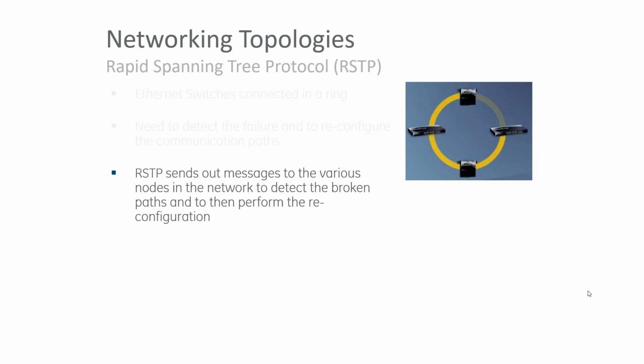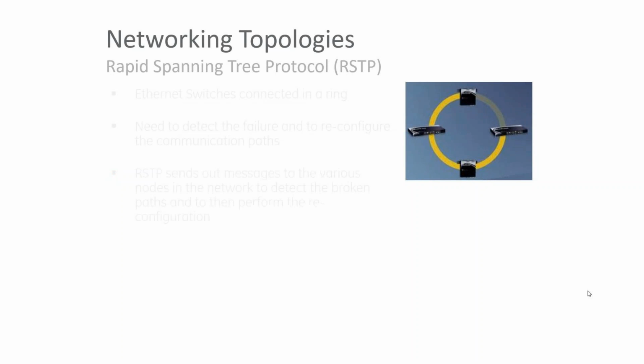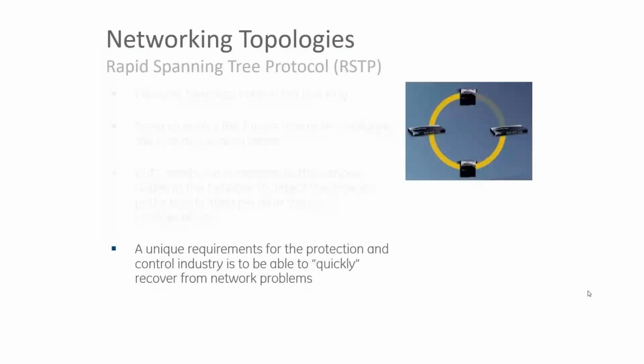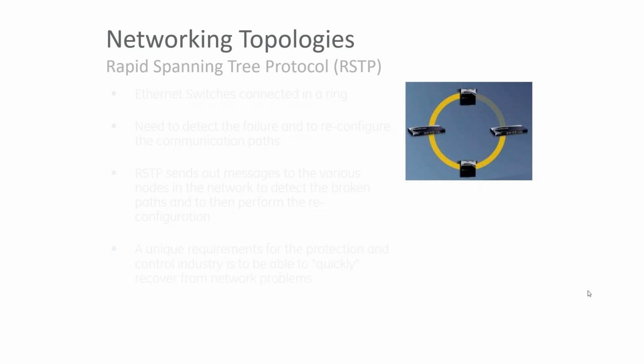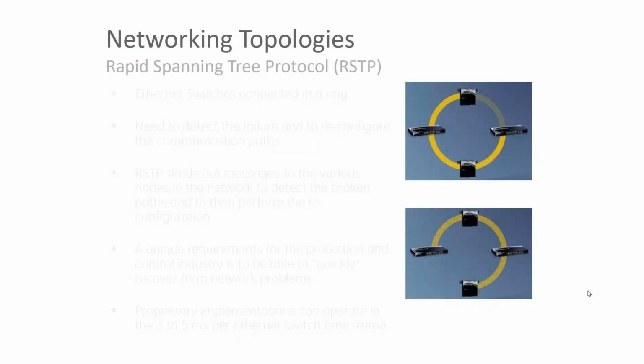It's just saying logically within those switches are ignoring that link for now, because that creates a loop. And what it does is, if there's a break somewhere else in the ring, it re-enables that loop with the shadow on it. So now it re-enables that loop, and now all the devices can connect to each other again. One of the drawbacks to RSTP is a finite time between when that loop breaks, determining when the break happened, and the recovery of the other loop.